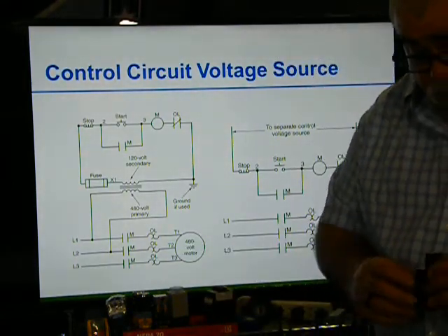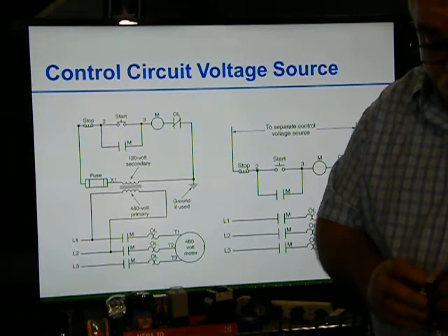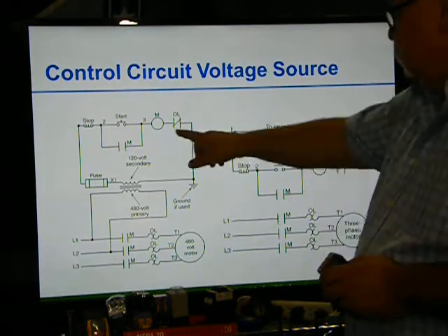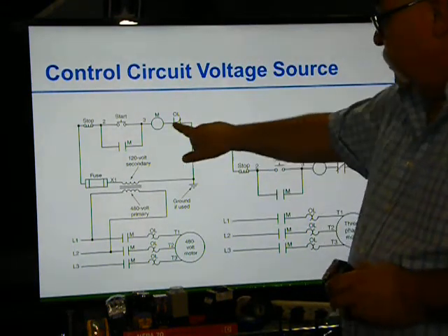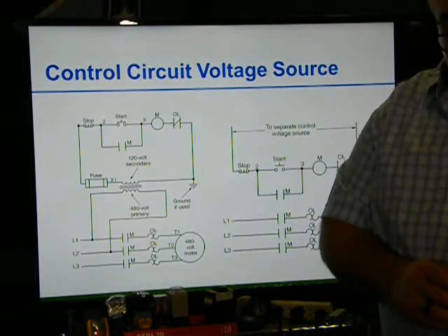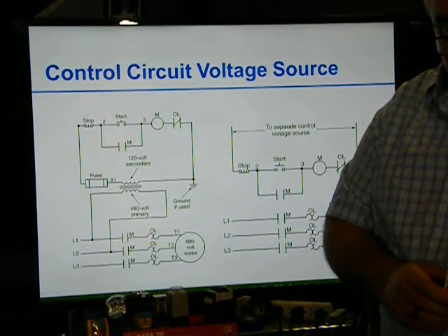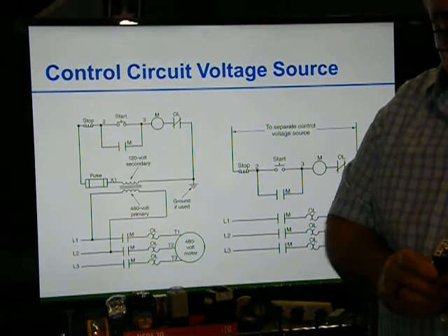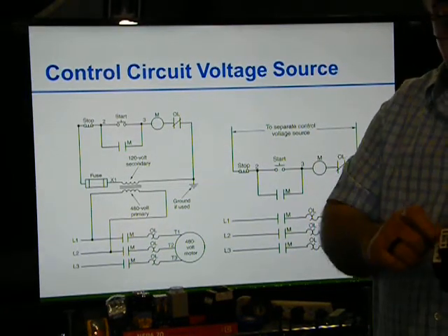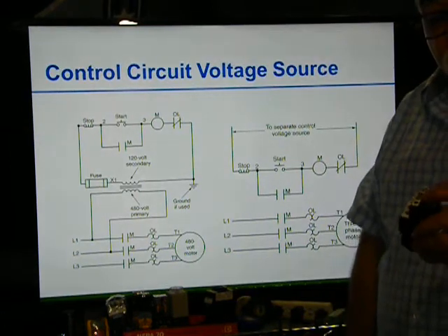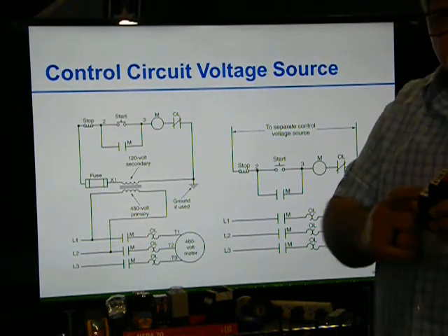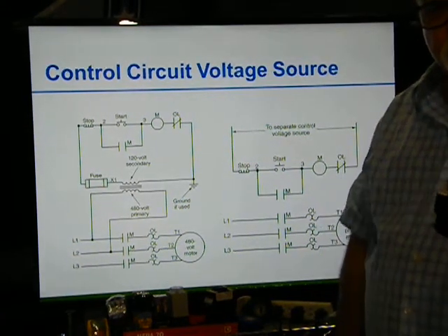Normally closed. I got 95 and 96. So I can bring in the 95, go out the 96. This will always be on. Okay, if this trips out because the motor's getting too hot, all you have to do is hit that button to reset it. The little red button on top, that's your reset button. If this trips out, all you have to do is hit the reset button.